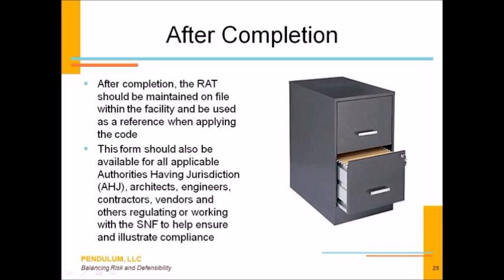And then once you make that determination, let's say that you're going to take that office space, turn it into a patient care space, and your team has conducted a risk assessment process and determined that failure of the electricity or the electrical delivery system in that newly remodeled space, that's now going to be a patient care area, is going to qualify as a category 2 requirement. Once you look at NFPA 99 to determine how you're going to remodel that space and what your code parameters are, you would have to follow all category 2 requirements for that space when it comes to the electrical system. Let's say for whatever reason you said failure of a plumbing system within that space would be a category 1 risk. That would mean that in the plumbing section of NFPA 99, you would have to follow all category 1 guidance for that space. I know, it's as clear as mud, but once you get into the handbook, you'll be able to see exactly how to apply this risk assessment process.